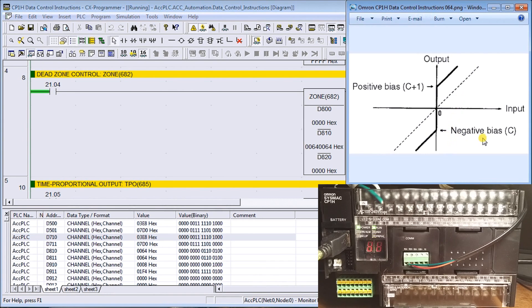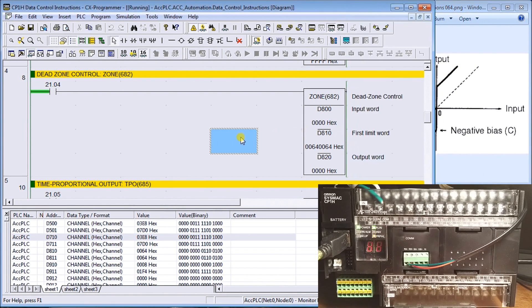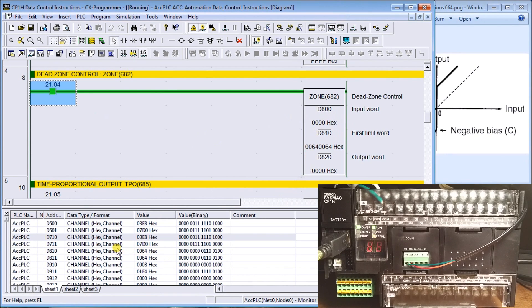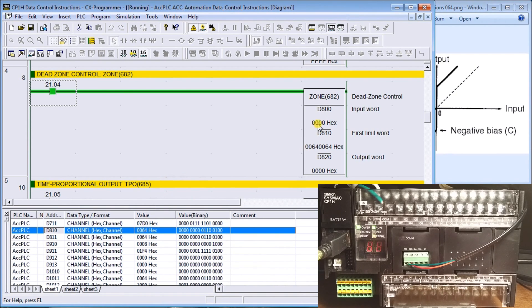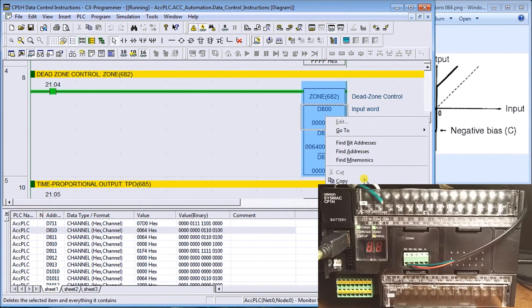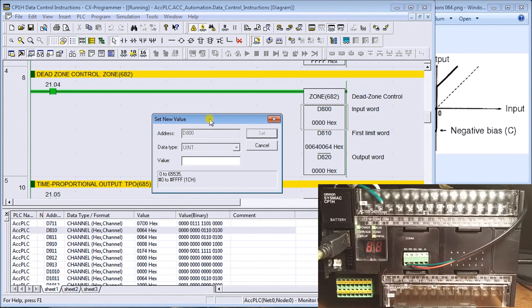Next is dead band zone, which works similarly but includes a negative bias and a positive bias. Any number put in will include that number — anything below zero gets a negative bias, anything positive gets a positive bias. So the output either goes up or down, skipping that middle area. In our zone example, we have a negative bias of 100 and a positive bias of 100, which is 64 hex.